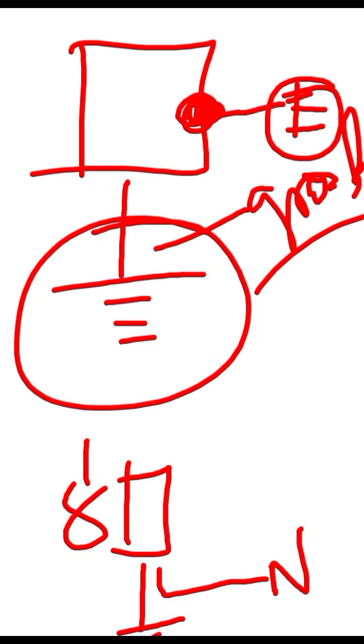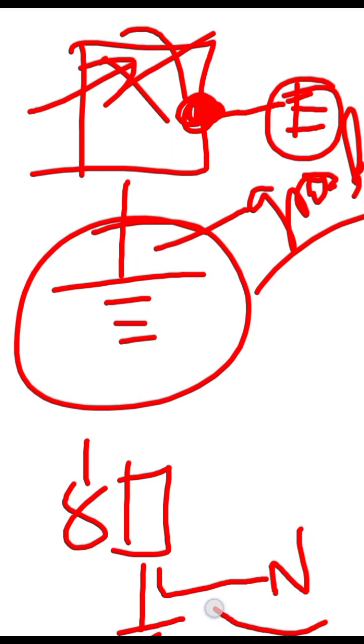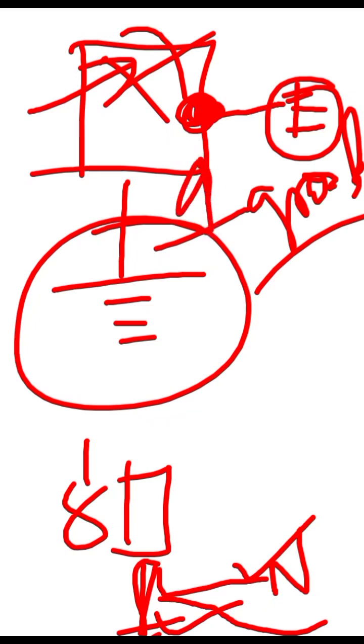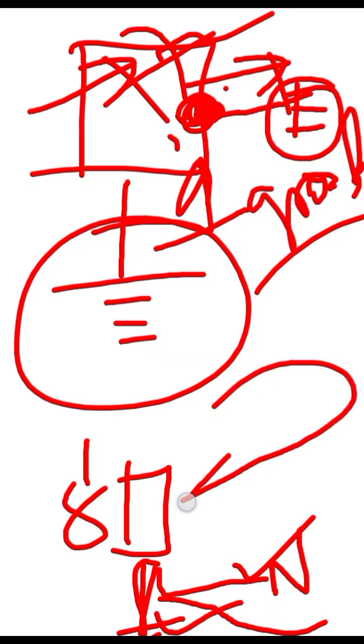So that tells you something, that whenever the casing becomes live as a result of an electrical fault, electricity travels back. It's like it's completing a path, but now through a different alternative cable. We can say basically that the earthing wire is an alternative of the return. Because the actual return is inside the electrical appliances in the load components, it can't return at that point, because the casing, which is independent of the neutral in the enclosures of the load, is in contact with the live. Therefore, we need an alternative path to complete a circuit that is not through your body. And that's how an earthing wire basically is originated, and that's basically how it protects you.